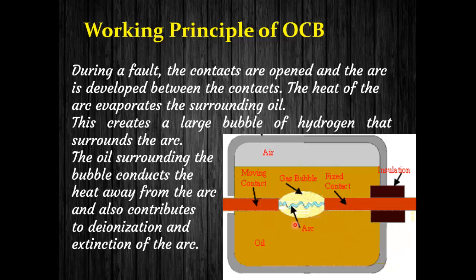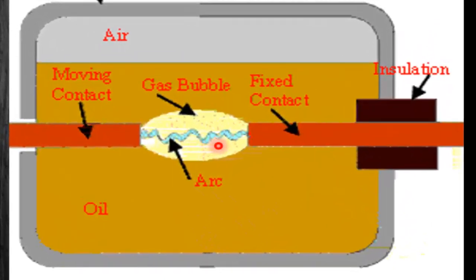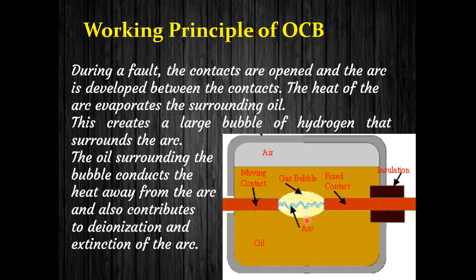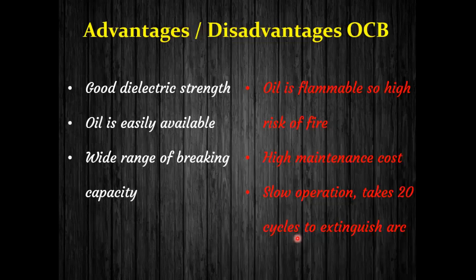In the OCB, there is a chamber with fixed and moving contacts. When a fault occurs and the contacts separate, an arc is produced. The heat of the arc evaporates the oil, creating a large bubble of gas which mainly consists of hydrogen. This bubble surrounds the arc from everywhere, and the oil surrounding the bubble conducts heat away from the arc, helping to cool, deionize, and extinguish the arc.